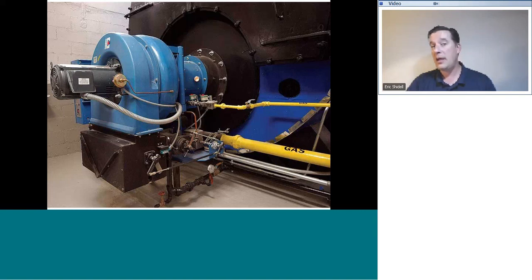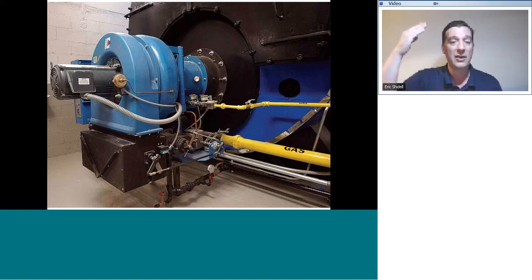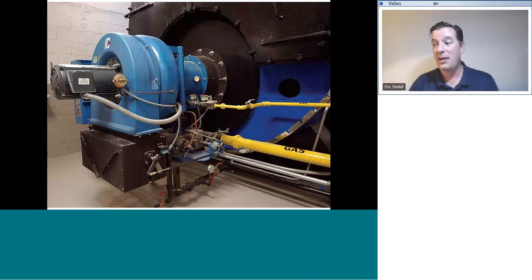Really bad, serious stuff. I've seen examples where, not personally, but I have seen pictures of where a big boiler like this, due to a misfire, will actually leave the building. They're usually installed in outside walls for that reason, of just a single layer of a block, so that this boiler, if it decides it wants to go for a walk in the parking lot, it can without completely destroying the building. And sometimes they will. So don't be the person responsible for that. Learn to leave well enough alone on big systems like this.